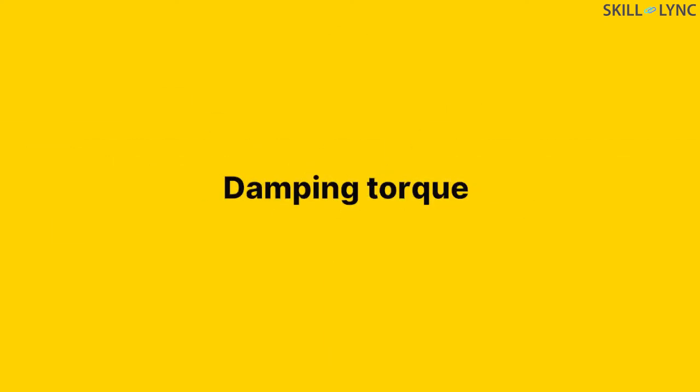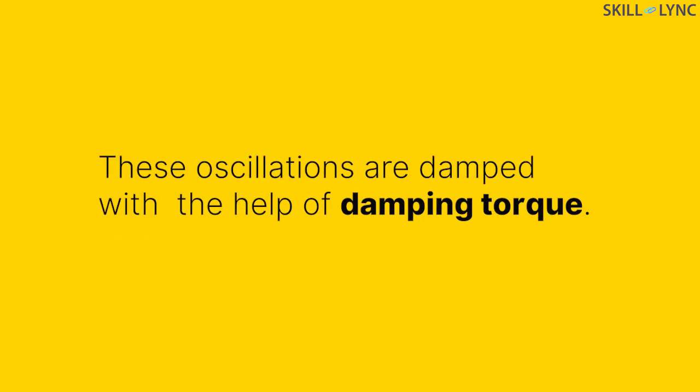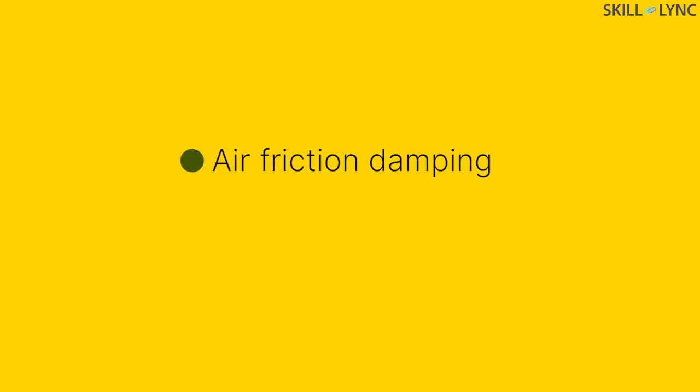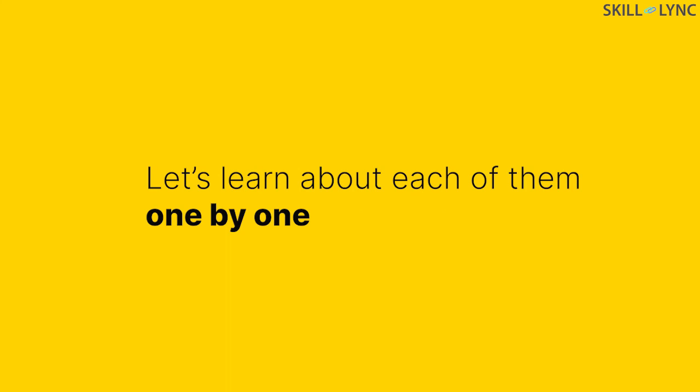Now, moving to the third and final torque on the pointer which is the damping torque. When the controlling torque and deflecting torque acts on the pointer due to inertia, the pointer will oscillate before it comes to rest. These oscillations are damped with the help of damping torque. Damping torque can be provided by air friction damping, eddy current damping and fluid friction damping. Let's learn about each of them one by one.